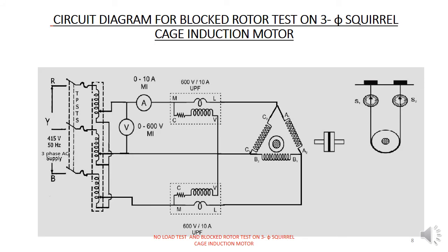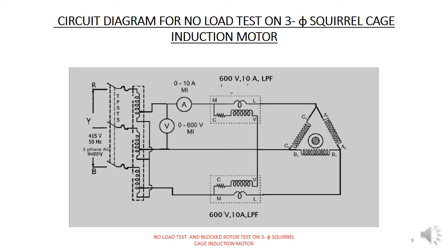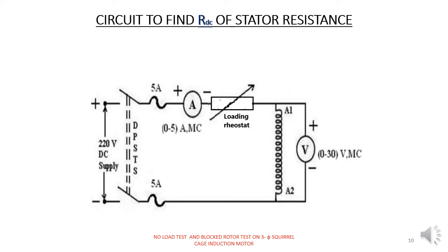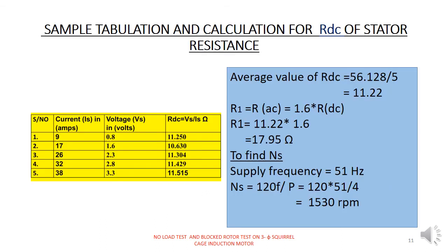This is the circuit diagram for block rotor test on 3-phase squirrel cage induction motor, and the circuit diagram for no load test. This is the circuit to find RDC of stator resistance, and a sample tabulation and calculation for RDC that we did in our laboratory with the students. Here we must find current, voltage and RDC, and from the average value of RDC we can calculate R1.